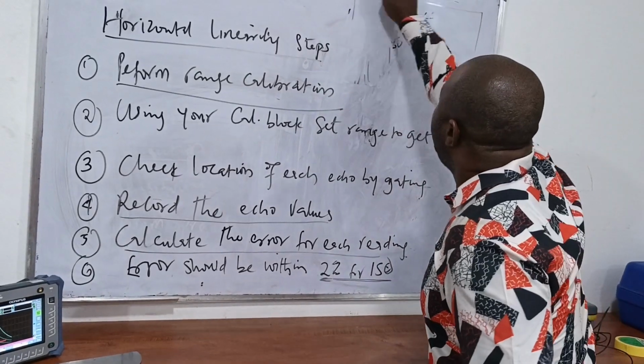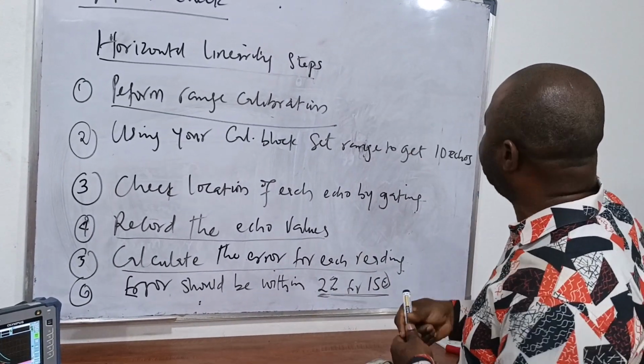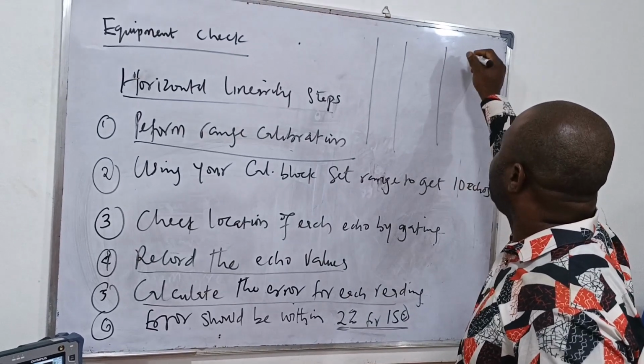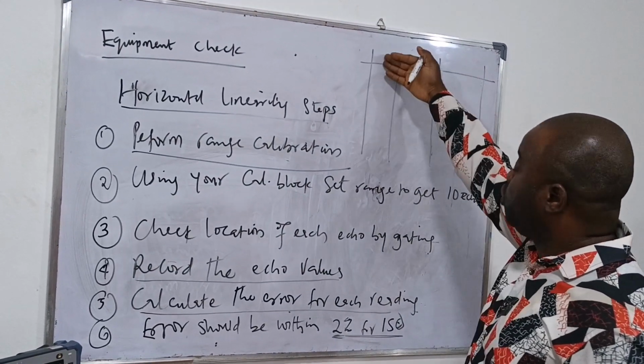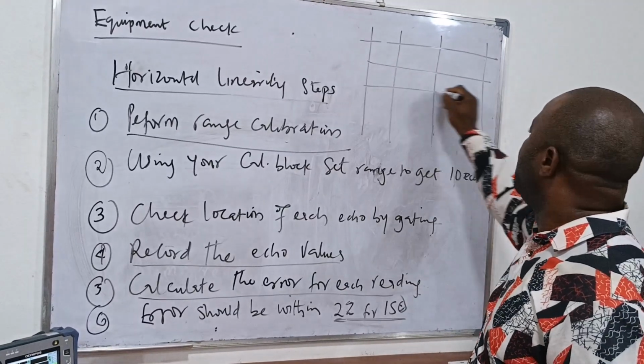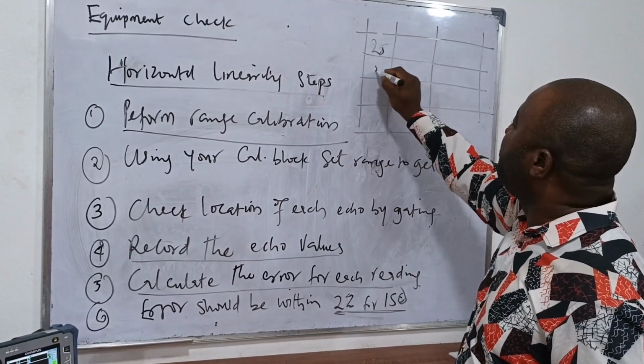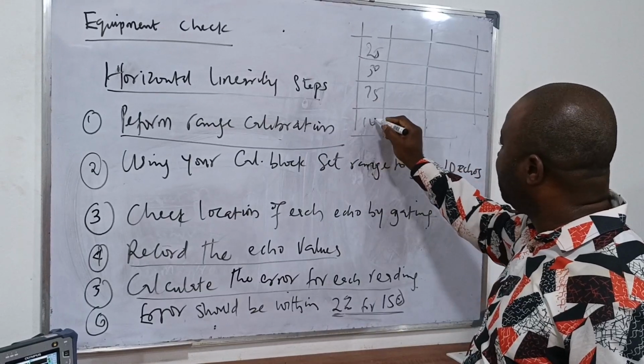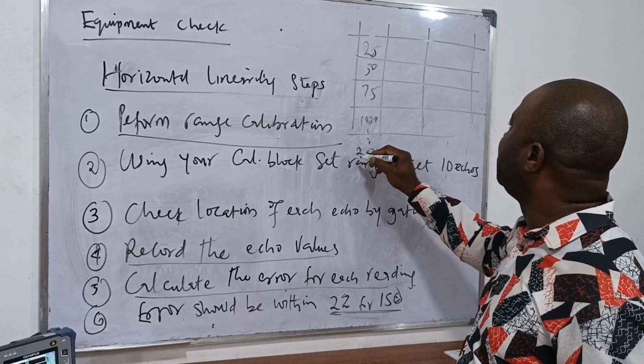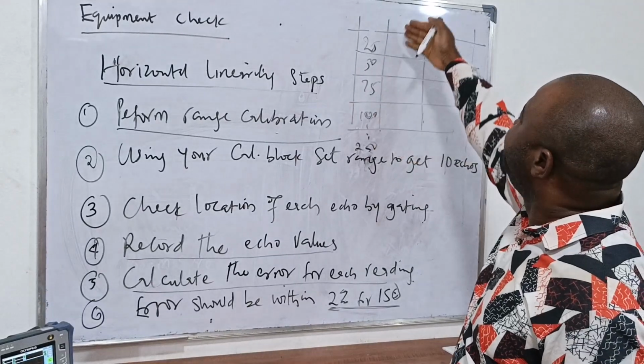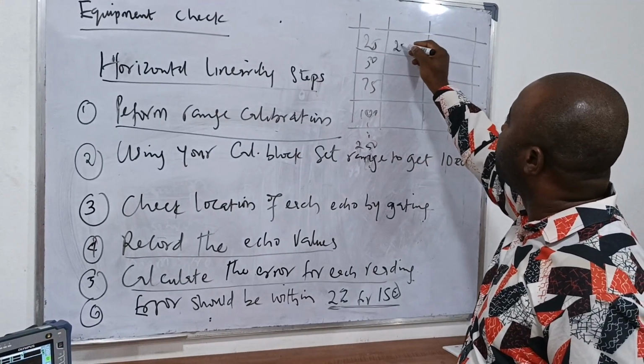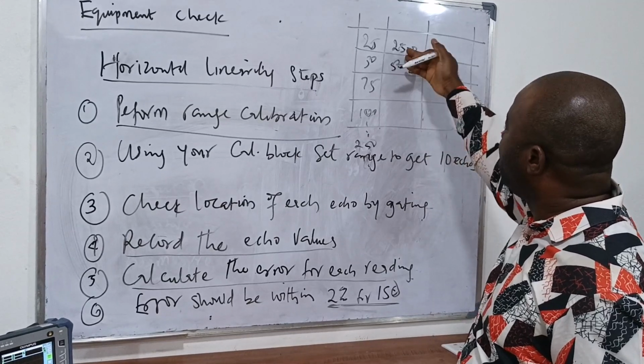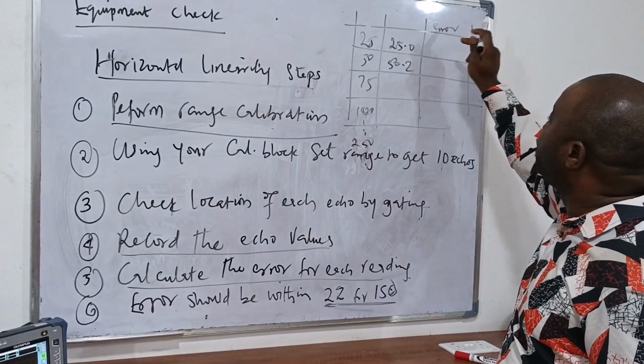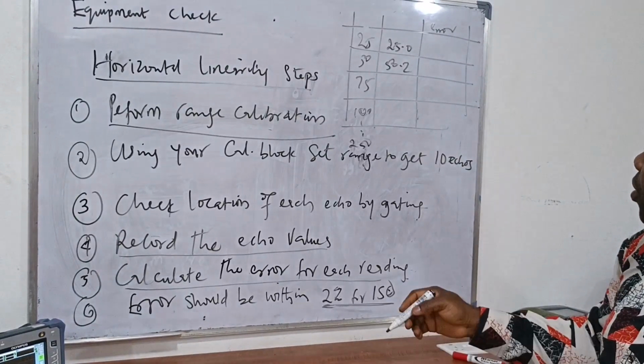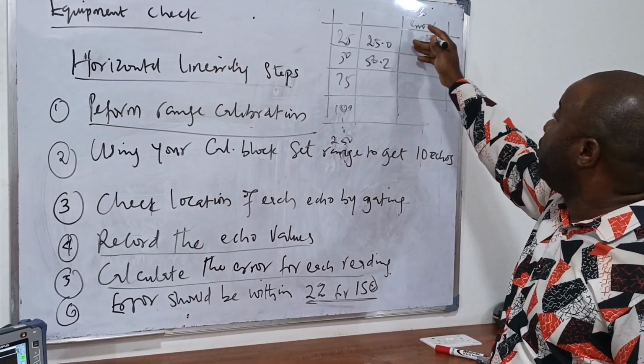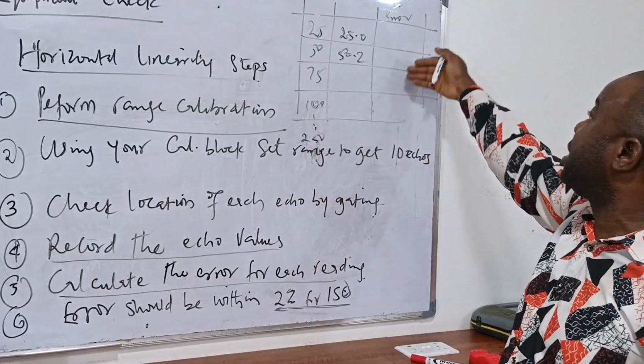So what do you do next when you have these values? You are going to have a table like this, with 10 readings from 10 echoes. So I have 25, 50, 75, 100, all the way to 250. This is my thickness. Then the readings you got, you need to input them here: 25.0, 50.2, and so on. Then the next thing you are going to do is check for the error. How do you calculate percentage error? Of course, before you calculate percentage error, you need to get the error.